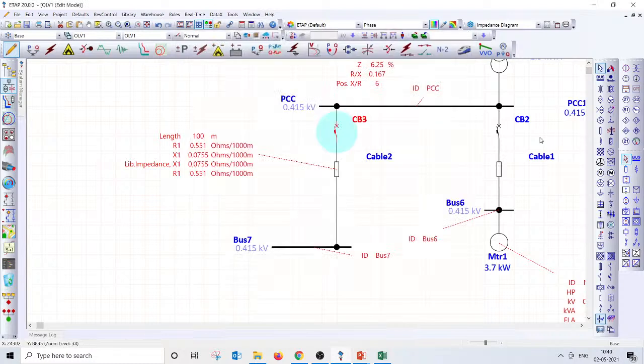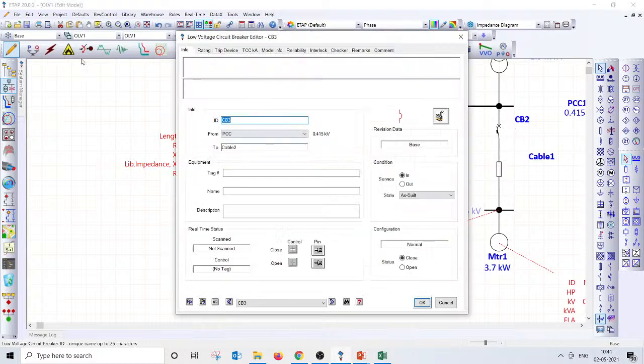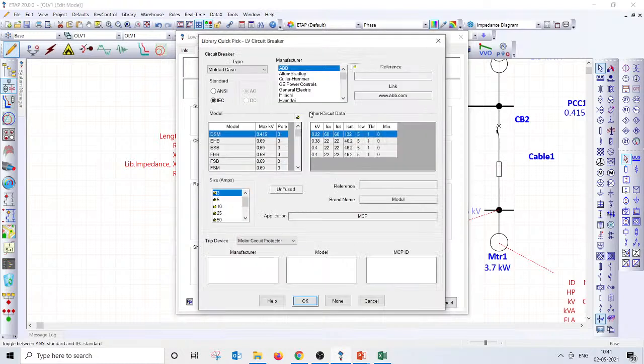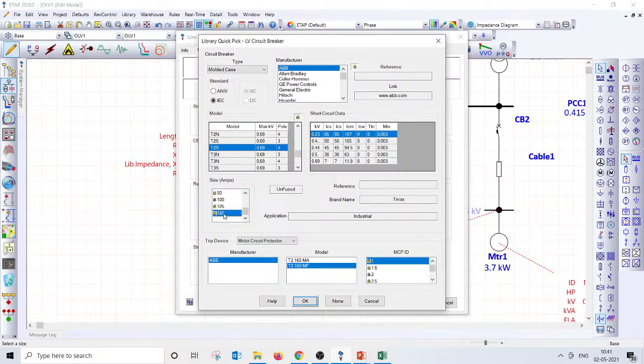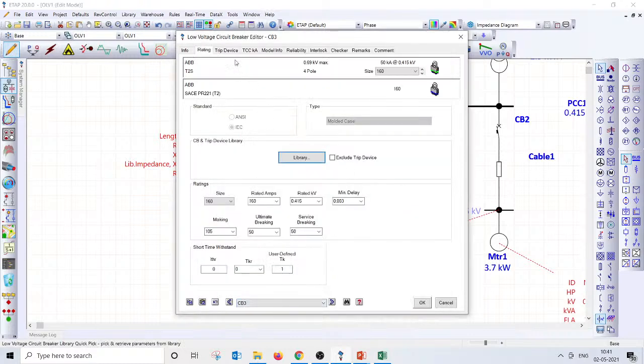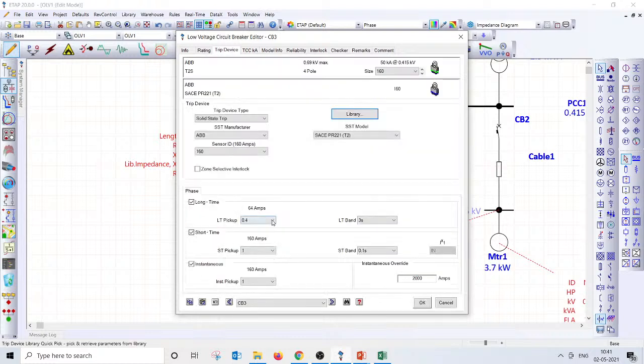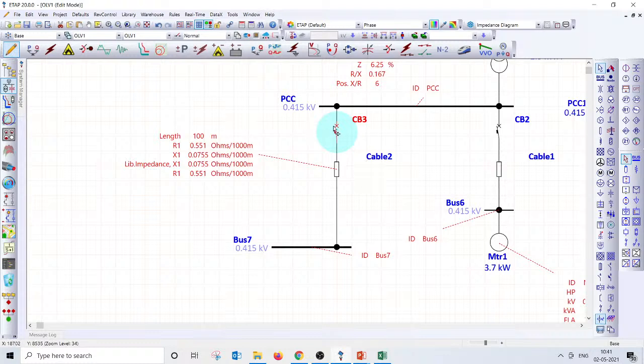So if I just copy this, we can probably draw something new here. I'm going with an ABB again, just to keep the assumption that it's the same switchgear and the same manufacturer has manufactured this. Say I'm going with a T2S, and let's say 160 amps, even with a solid state release. Let's look at what problem we may anticipate. Here we need to ensure it's coordinated with the downstream, and at 3 times the pickup you are giving, for example, 0.1 second or 0.25 seconds, because this coordination has to be done with the downstream. And also try to check the short circuit withstand.